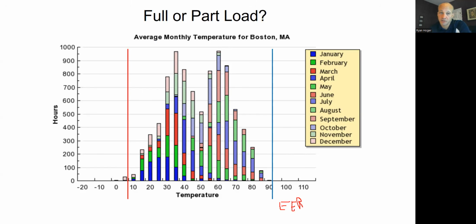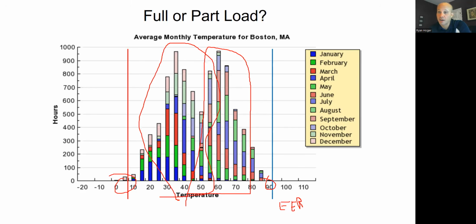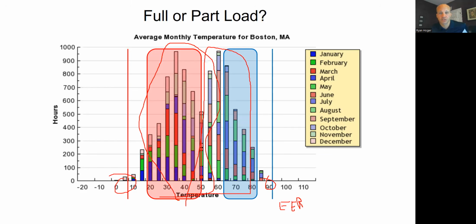As you can see, here's part load cooling, here's part load heating, right? So how efficient are you at all these hours? Because these hours don't matter. I mean, they matter. I got to size my equipment to handle those days, but I don't care if it's super inefficient to heat my building when it's 0 degrees. I don't care. If I'm saving heat energy all the other days of the year, I'm good with that, right? So just kind of keep that in mind. Instead of my crude drawings, I guess I could have just showed that, right?